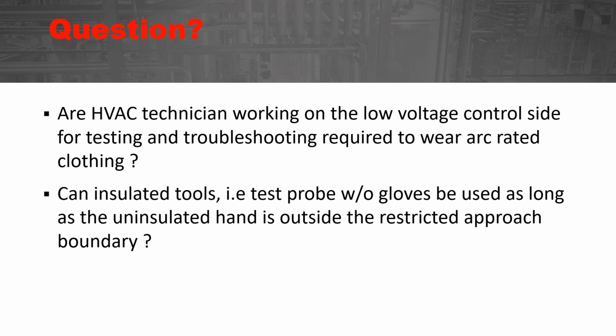So if someone is within the arc flash boundary, say they've opened the cabinet up, there's the low voltage control, but there's also live electrical in that box as well. What is the arc flash boundary? Say even if the arc flash boundary is 12 inches, then someone's hand, if they're going to be within 12 inches, then the hand has to be protected against the arc flash.